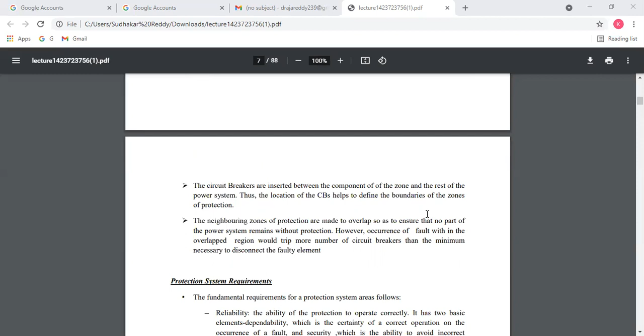Generally, the fundamental requirements for protection of a system are as follows: first reliability, second speed, then selectivity and cost. These are the main requirements for protection of a power system. First, reliability: the ability of the protection system to operate correctly. It has two basic elements: dependability, which is certainty of correct operation on the occurrence of a fault, and security, which is to avoid incorrect operation.